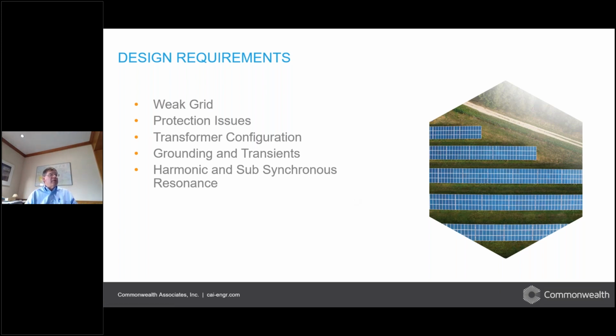There are a lot of design requirements that are required to interconnect a solar project. Now, in the top bullet there is a weak grid. We measure grid strength typically by a technical measure, the short circuit ratio. So if your short circuit ratio gets below 5 or 3 or thereabouts, particularly grid following inverter based generation has a difficulty staying online. So weak grids demand particular design requirement types of things to get your solar interconnected.